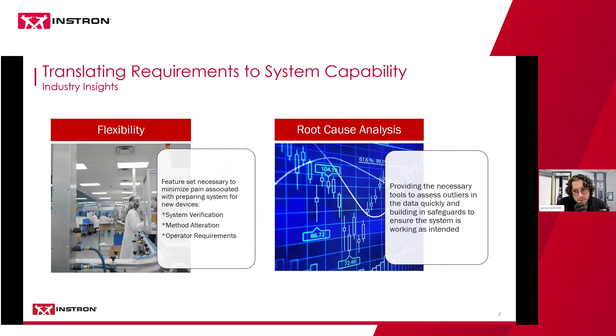When you look at the marketplace, at what customers are doing now to test auto injectors, there's a good portion of the market who is still doing a lot of testing in a somewhat piecemeal manner, where they have different test systems to evaluate different EPRs for their device. So this is not an uncommon scenario at all, but there are cases where a customer has a standard universal test system to measure cap removal and maybe activation force. They then take the fluid that comes out from a beaker and put it into a separate balance to get delivered volume. They develop their own machine vision camera systems to measure the injection time and the needle depth, and then maybe have a microphone for the click detection. So, that could be 3, 4 different systems doing all of those tests.